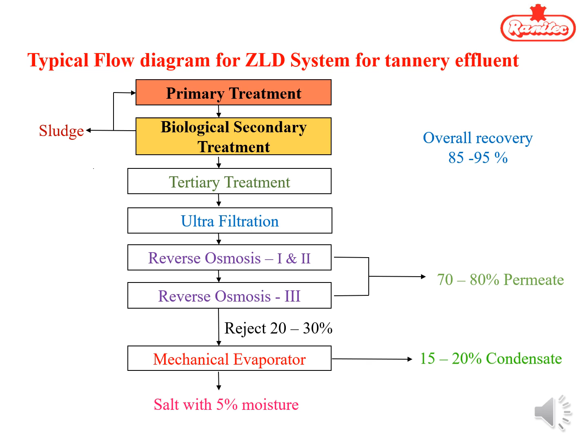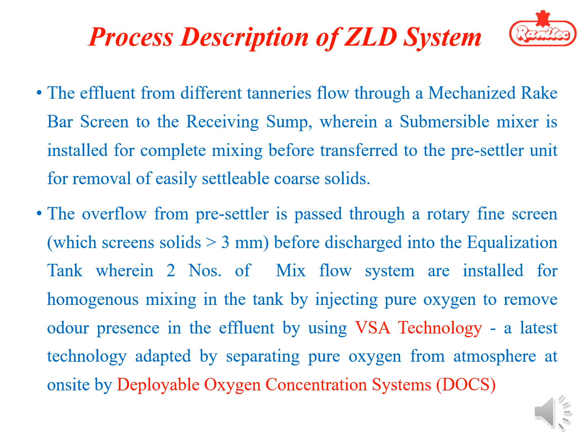This is the process description about the ZLD system. The effluent from the tanneries flows through the mechanized bar screen to the receiving sump, wherein a submersible mixer is installed for complete mixing before transfer to the pre-settler unit for removal of easily settleable solids. The overflow from the pre-settler is passed through a rotary fine screen which screens solids larger than 3 mm before being discharged into the equalization tank, wherein 2 numbers of mixed flow system are installed for homogeneous mixing in the tank by injecting pure oxygen to remove odor present in the effluent, using VSA technology, a latest technology adopted by separating the pure oxygen from atmosphere on-site by a deployable oxygen concentration system. It is called DOCS.